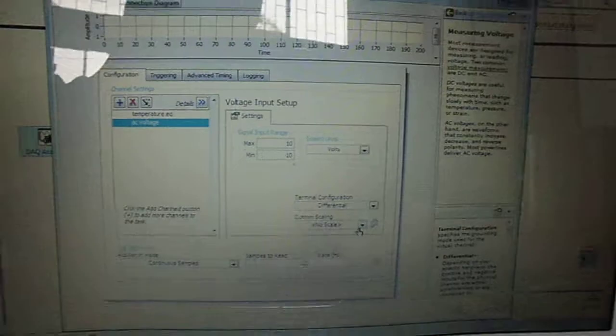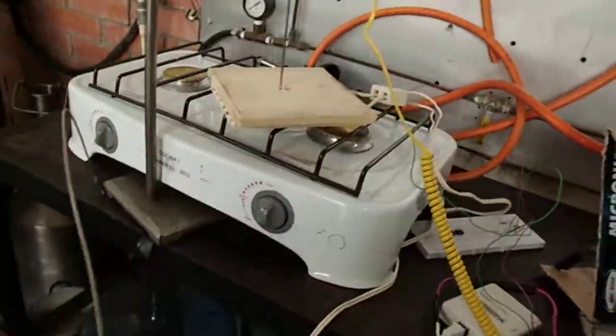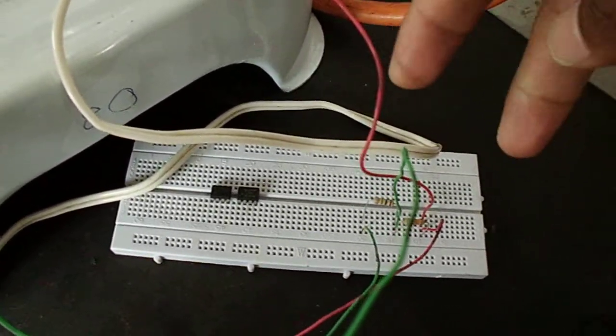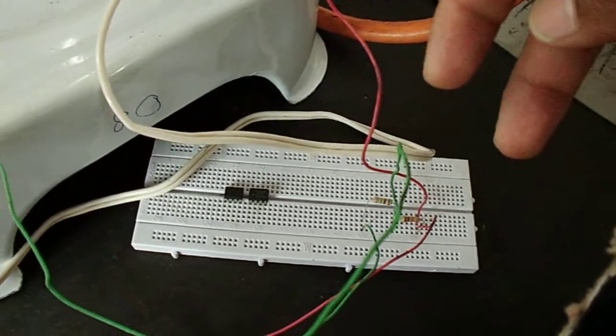The unit is in voltage. I'm working with differential. Why differential? Because it's not with respect to ground — I'm measuring the signals point by point, voltage point by point from this resistance. For these reasons, you should choose differential. Don't forget that. Continuous sample — it's OK, because it's analog input. Samples to read: 100. One kilohertz as the rate.